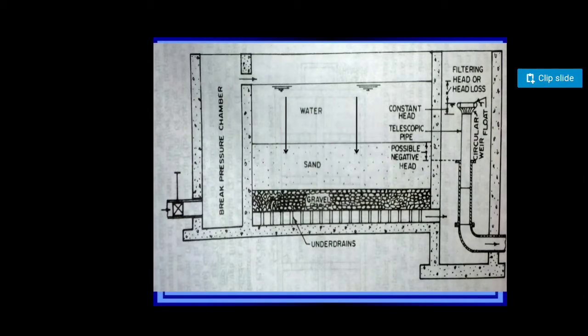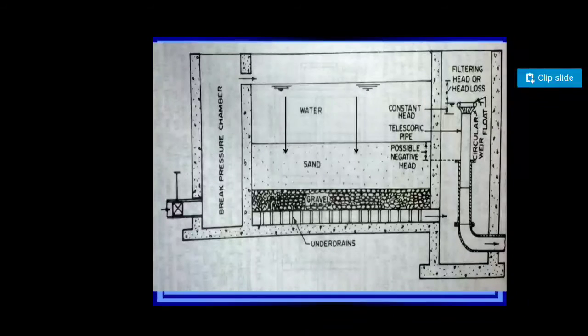What also happens here is that a layer of bacteria or other microorganisms develops over the suspended solids retained over the filter media, and this layer of microorganisms is called the Schmutzdecke, right? This Schmutzdecke starts to break down the organic material coming with the influent, and that organic material is decomposed by the bacteria which have settled in the form of Schmutzdecke. So now this process is not just treating the water by filtration, but is also treating it through biological activity, right?